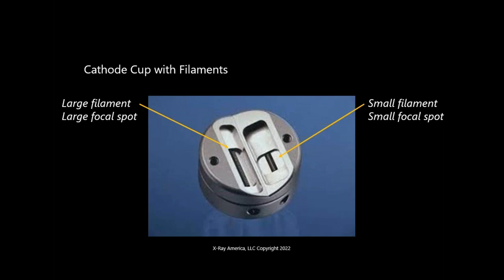That's really true. From the tech point of view, you learn real quick, even when you have a brand new system, they just replace both your tubes. They tell you it's the same tube, the same manufacturer. And I guarantee you, one will shoot better than the other, every single time. And you learn real quick which one you want to use. You're going to have to see that clinically, yes, you can see the 30% difference in image quality. And it's not a difference between the two generators?